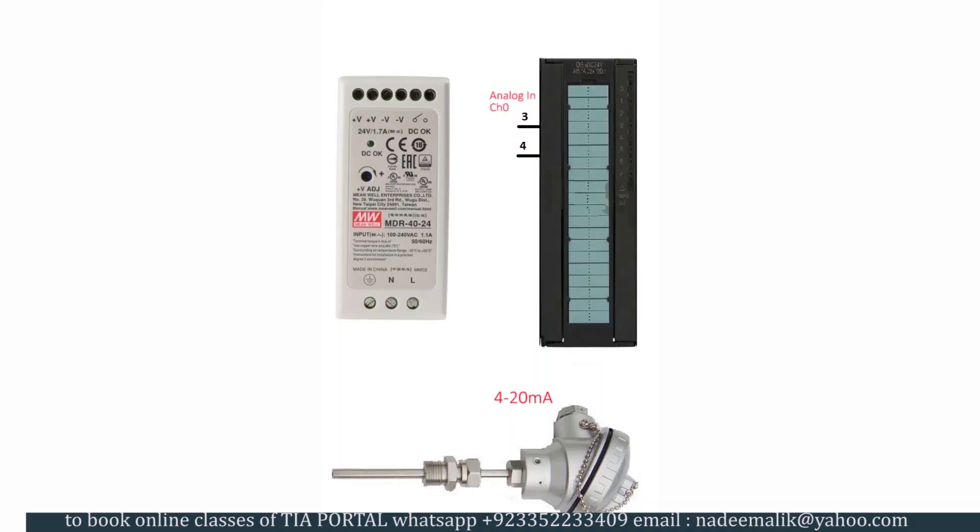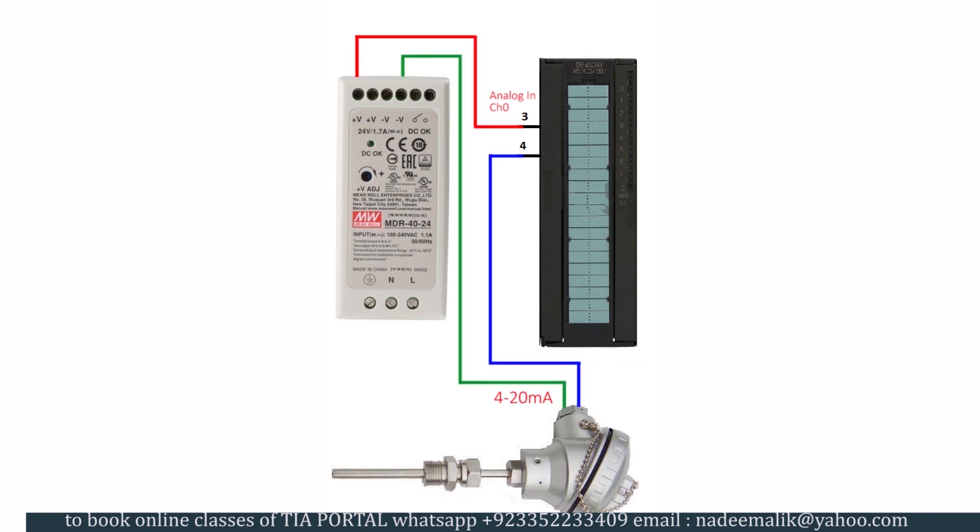First of all, have a look at the wiring of the temperature transmitter with the S7-300 PLC. As we have a two-wire analog transmitter, the wiring is really simple and straightforward. We have connected 24 volt power supply, temperature transmitter terminals, and analog input channel 0 in series closed loop connection.